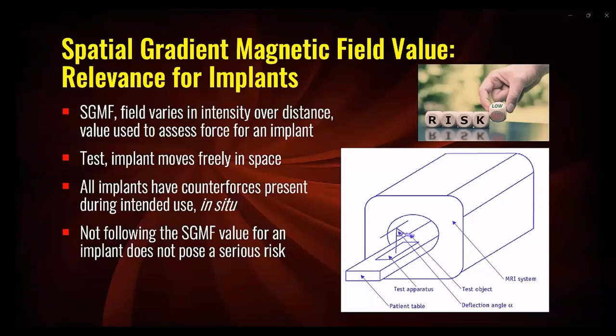It should be noted that in virtually every case, once the medical product is implanted, there are counter forces that act on the implant which are associated with the surrounding tissue or by virtue of having some form of fixation, such as those associated with sutures, screws, or other form of fixation that provide retention of the implant, that all contribute to a margin of safety with respect to the translational attraction or force-related issues. In consideration of this information, it should be realized that not following a particular spatial gradient magnetic field value for an implant does not necessarily pose a serious risk to a patient relative to magnetic field-related force because of the aforementioned counterforces that are present.